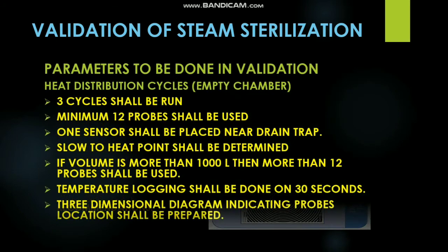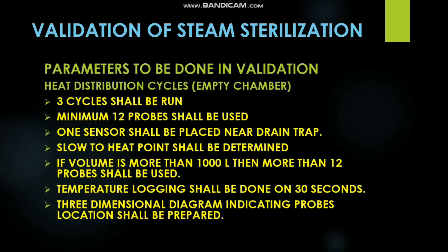Now next comes heat distribution cycles, or empty chamber cycle, empty chamber study. In this, 3 cycles shall be run, minimum 12 probes shall be used, 1 sensor shall be placed near the drain trap, and slow to heat point shall be determined.